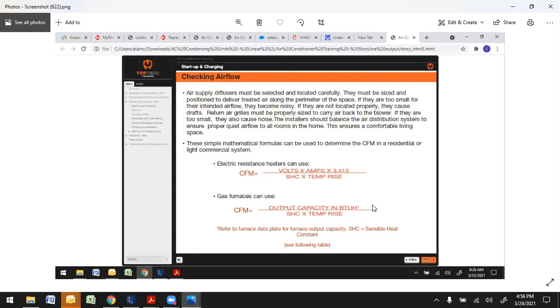So we'll say if you have an 84,000 BTU output, 90% gas furnace, you'll take your 84,000, divide that by your sensible heat constant, which is 1.08, times your temperature rise, and then that will give you your exact CFM. If that CFM matches what you think is adequate, you're okay.